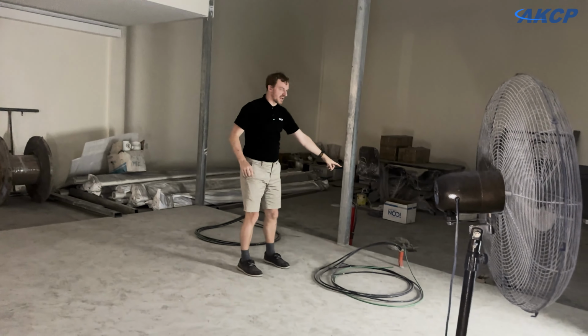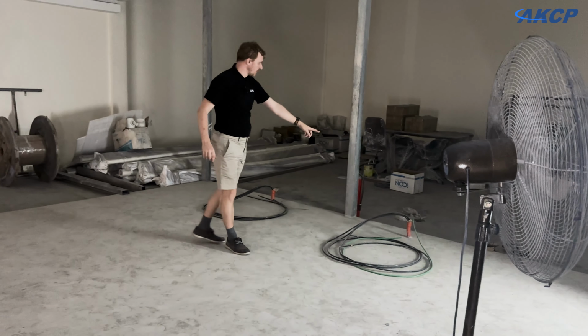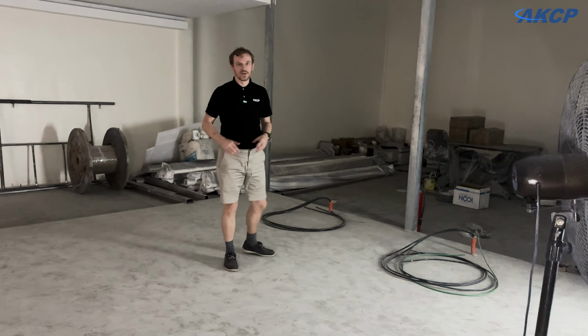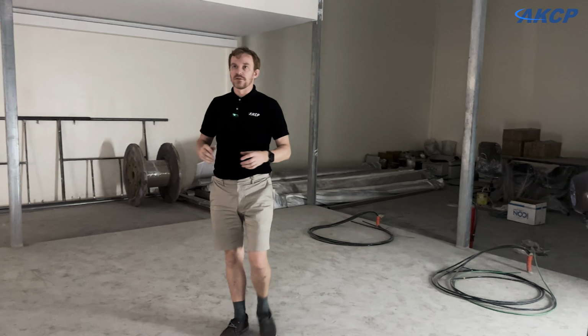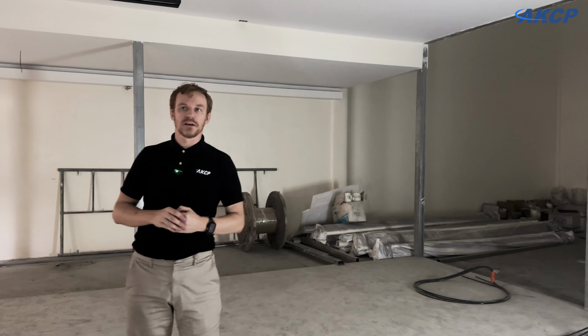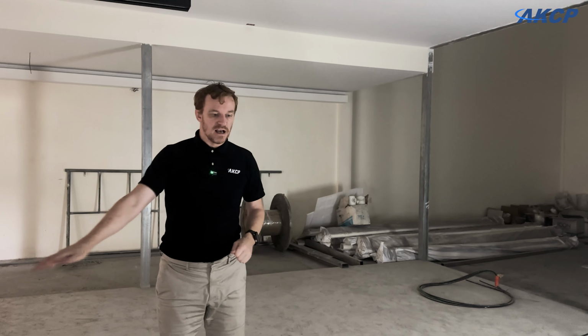So in this part of the data center, we will actually have a raised access floor and cold aisle containment, but we will not use the overhead bus bar distribution. Instead, the power will come in under the raised access floor, hence the provision for those wires there. Continuing on with the electrical works, we're aiming for another 7 to 10 days to have all of the electrical works finished.